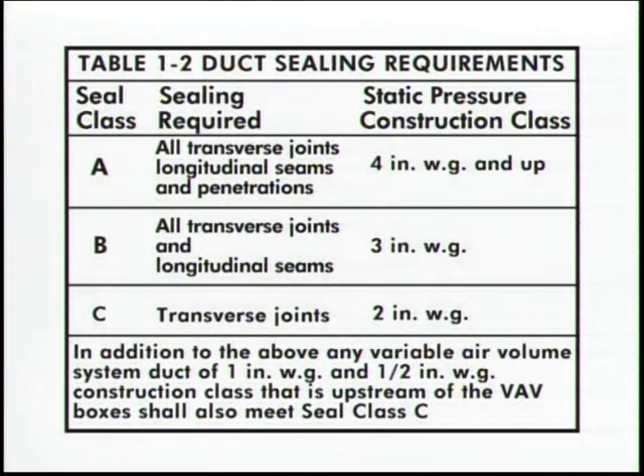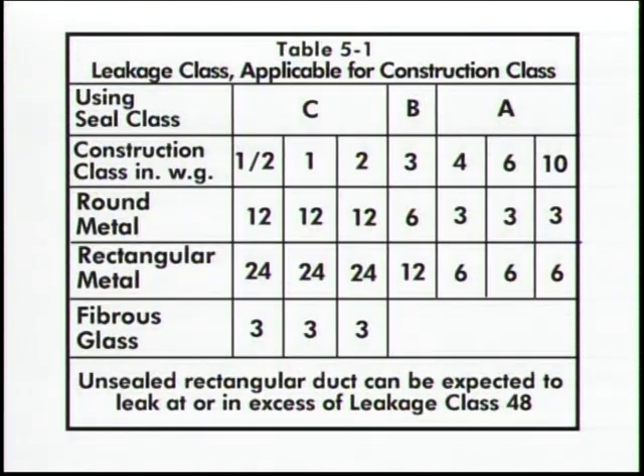Using duct air leakage tables found in the ASHRAE Fundamentals Handbook, the duct seal class must first be established. Then, using the proper seal class in the air leakage class table, the duct air leakage rate for sealed spiral ducts is half that of rectangular metal ducts, under the same duct system pressure conditions and the same duct perimeters.